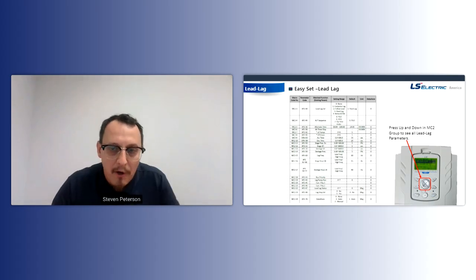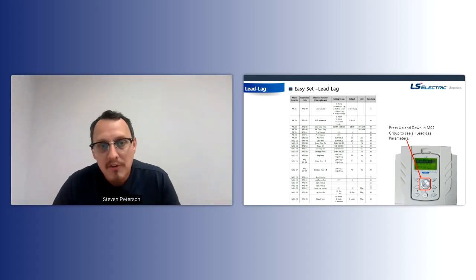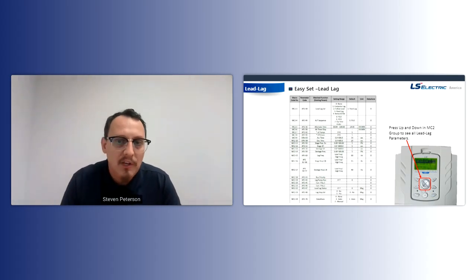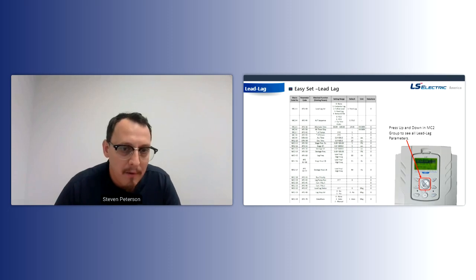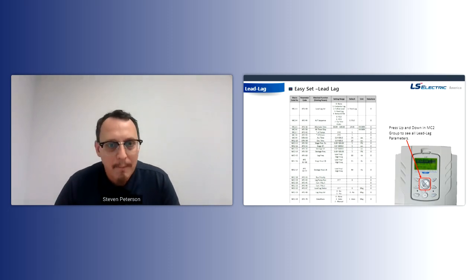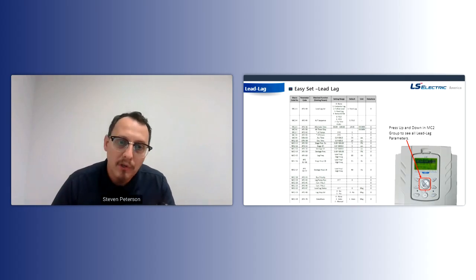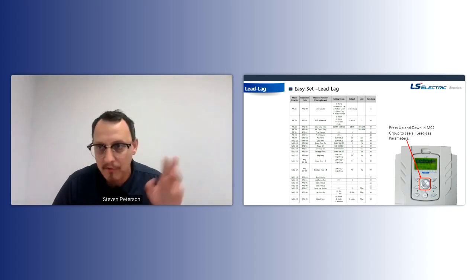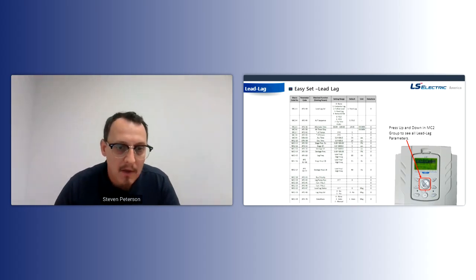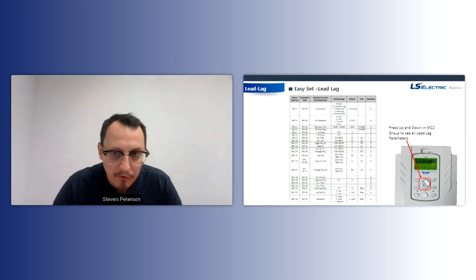And then when you get to this middle part of the list here, that's where you see your staging and your destaging. Staging is what do we need to program to pull on a pump? It's typically based on pressure, speed, and a delay time. And that's going to be the same thing for a destage. If our frequency goes low, our demand is met, and after a certain time, let's shut off the second pump, for example. So this is all fully programmable, so you can customize it for whatever your needs are.